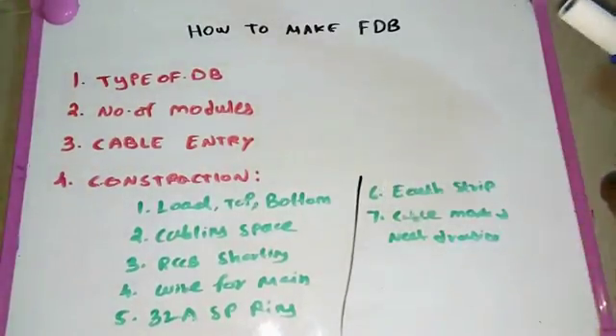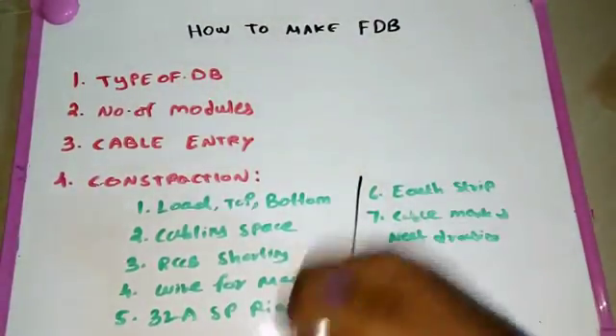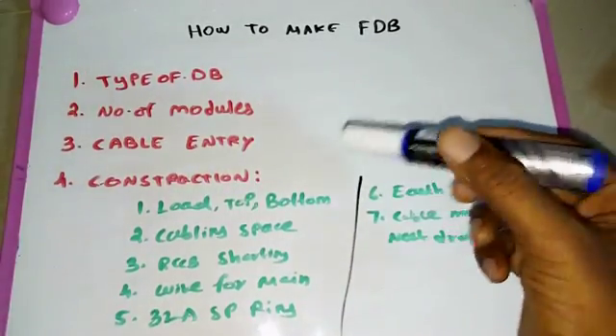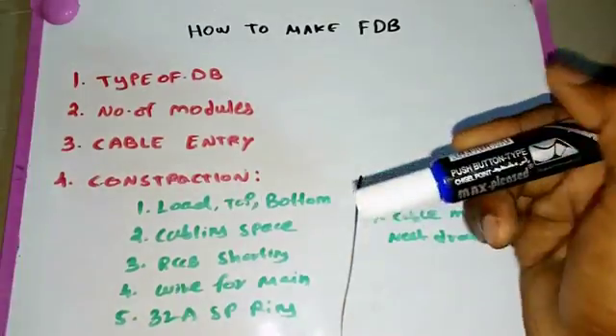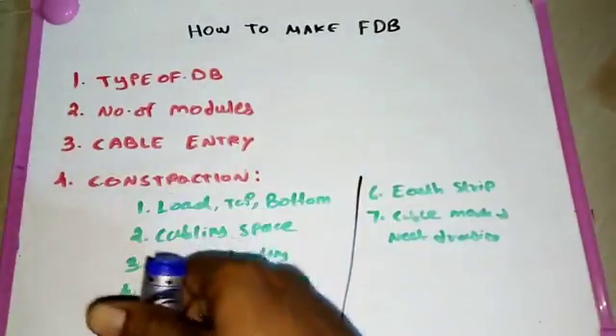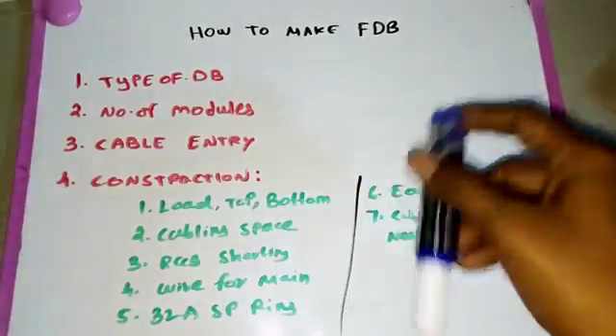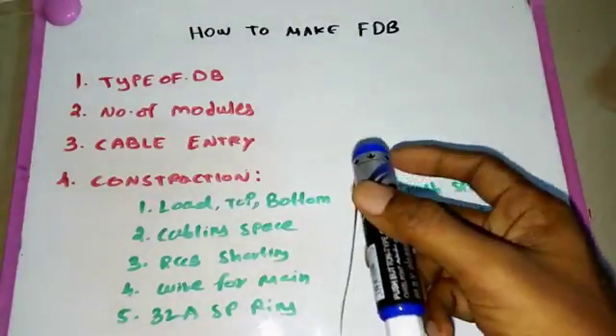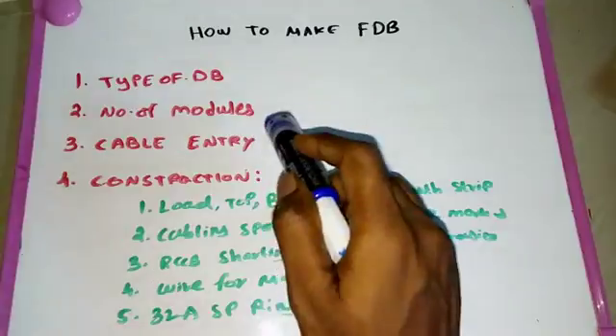The next consideration is cable entry — whether cables are coming from the bottom or from the top. This is very important for final DB construction. If the cable entry is from the bottom, we need to mount the isolator at the bottom side accordingly. If the cable entry is from the top, we mount the isolator at the top and then construct the other components.